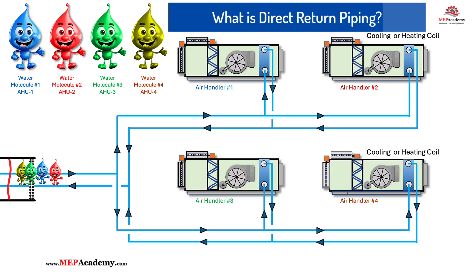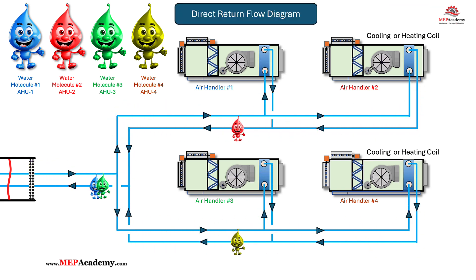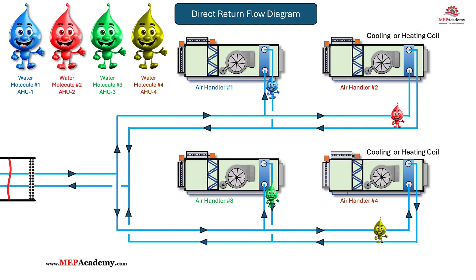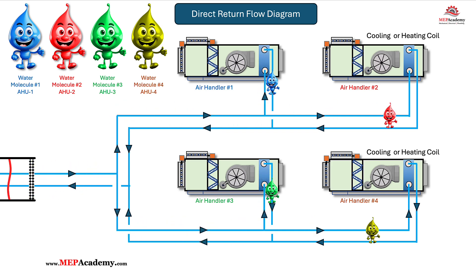What is direct return piping? In a direct return piping system, water flows to each air handler coil and returns along the shortest path. This means that the closest air handler coil to the heating or cooling supply source — such as a boiler or chiller — will have the shortest overall piping length, while the furthest air handler will have the longest piping route.